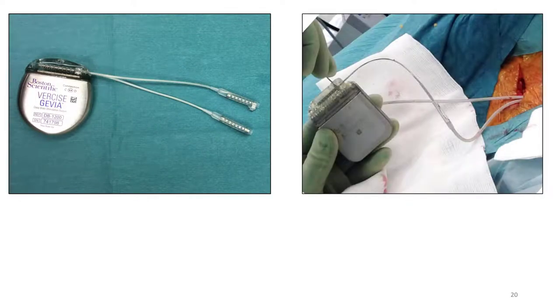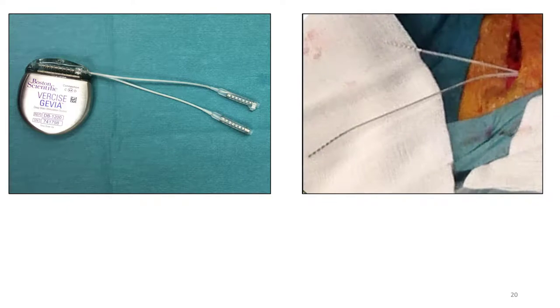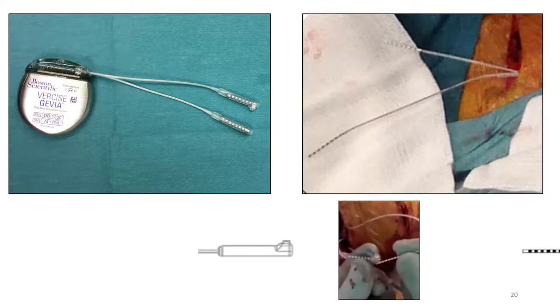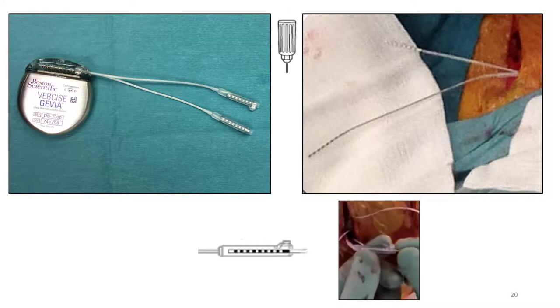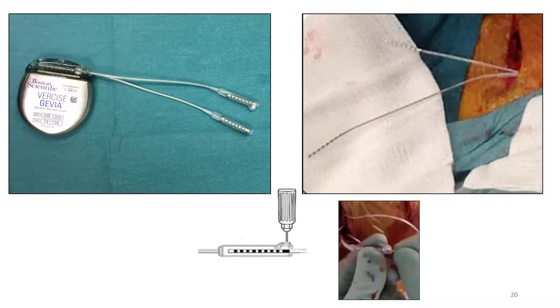We then remove the old IPG and disconnect it from the extension cables. The old extension cables are then connected with the adapter by inserting them into the new connector of the adapter and locking the screw.